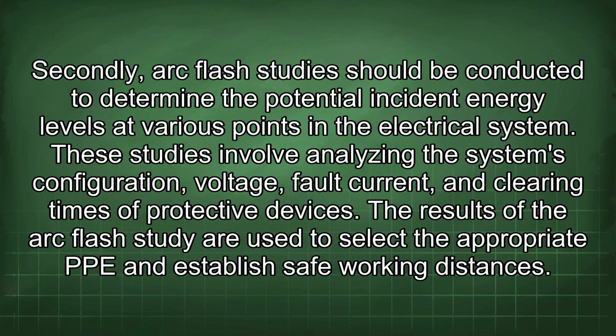Secondly, arc flash studies should be conducted to determine the potential incident energy levels at various points in the electrical system. These studies involve analyzing the system's configuration, voltage, fault current, and clearing times of protective devices. The results of the arc flash study are used to select the appropriate PPE and establish safe working distances.